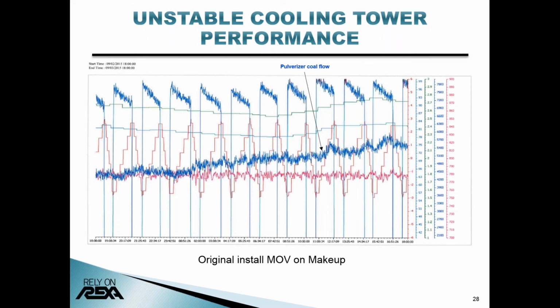This can be trended back in correlation to the water flow going to the cooling tower. Every time we shut off makeup water to the cooling tower, the water would increase in this main circ water, and we would lose performance in our condenser, increasing back pressure. The only way to make this up was to keep increasing coal flow into the boiler. As we increased the coal flow into the boiler, we also had to increase boiler air and furnace draft to compensate for the coal flow. Wow, it's just amazing how all this cascaded back just from basin water level.